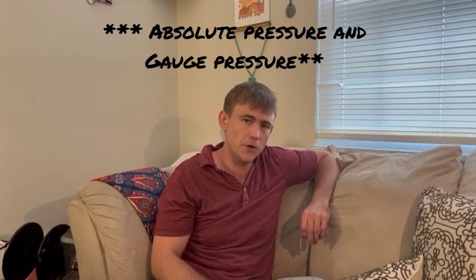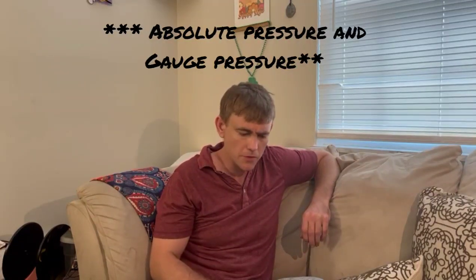So there's two main types of pressure. You have absolute pressure and gauge pressure. So you might have a sensor that reads in PSI-G, which is PSI gauge, or PSI-A, which is PSI absolute. Generally, most things are going to be in gauge pressure. So if it just says PSI, it's most likely reading gauge pressure.